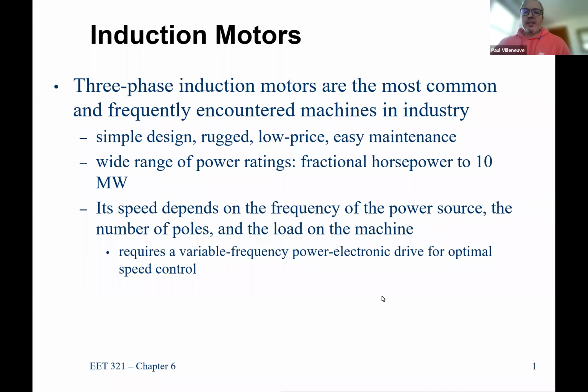Okay, so let's begin. We started to introduce this topic a little bit, sort of sneakily in lab. If you remember correctly, we were struggling to get the synchronous motor to start when we had the excitation winding energized, meaning the switch was in the closed position. What we found is that when the switch was in the open position, it would actually spin and rotate, but it operated at a lower speed than synchronous speed.